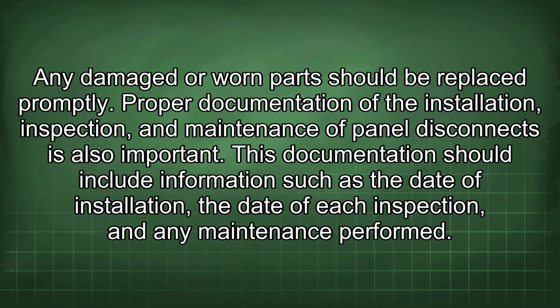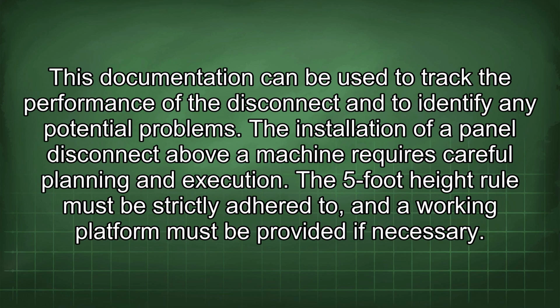Proper documentation of the installation, inspection, and maintenance of panel disconnects is also important. This documentation should include information such as the date of installation, the date of each inspection, and any maintenance performed. This documentation can be used to track the performance of the disconnect and to identify any potential problems.